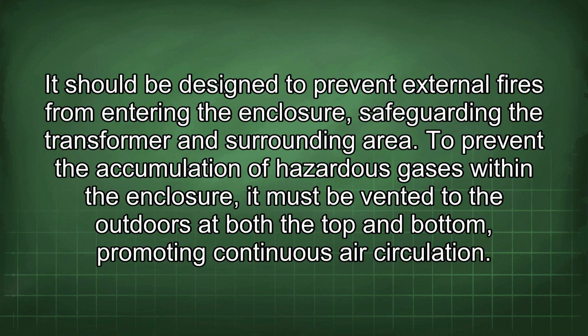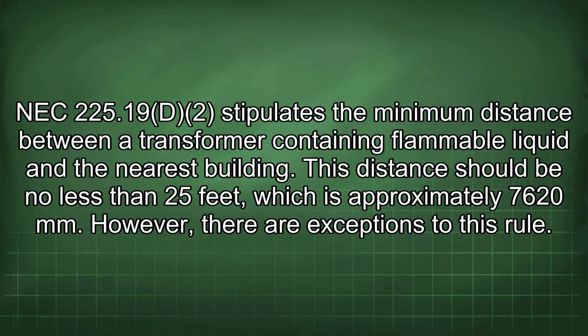To prevent the accumulation of hazardous gases within the enclosure, it must be vented to the outdoors at both the top and bottom, promoting continuous air circulation. NEC 225.19d stipulates the minimum distance between a transformer containing flammable liquid and the nearest building. This distance should be no less than 25 feet, which is approximately 7,620 mm. However, there are exceptions to this rule.